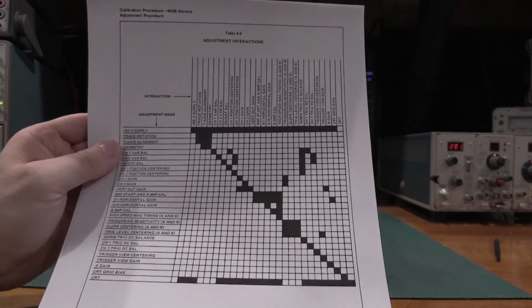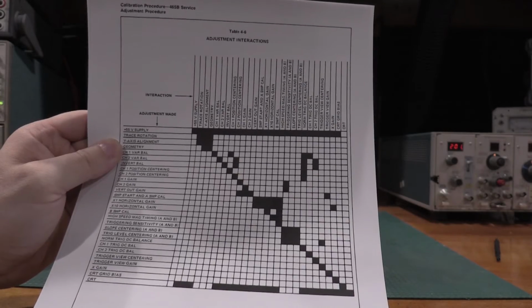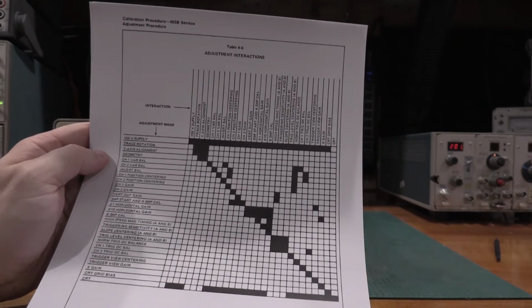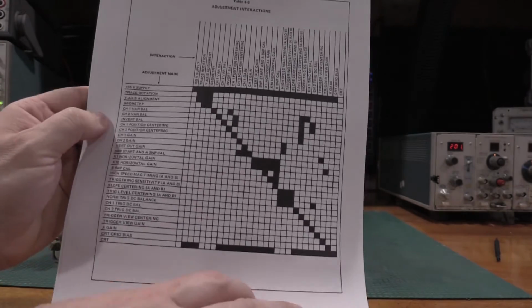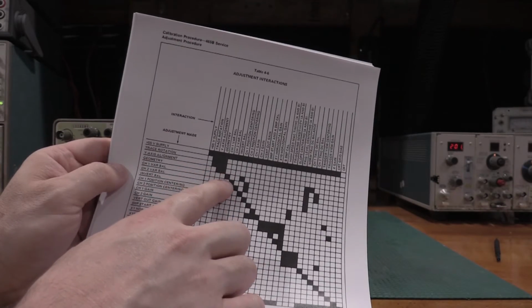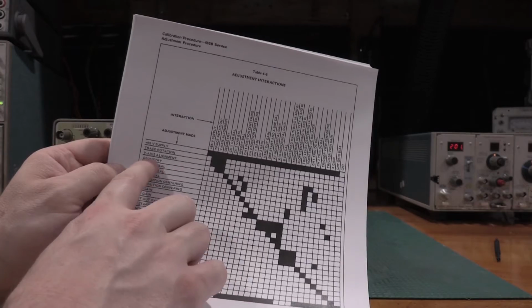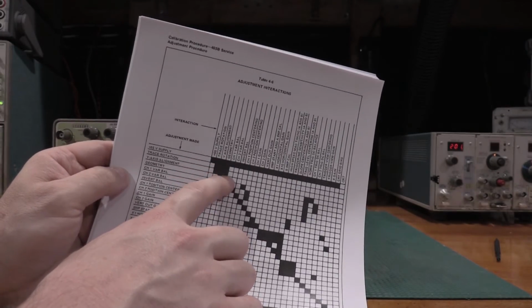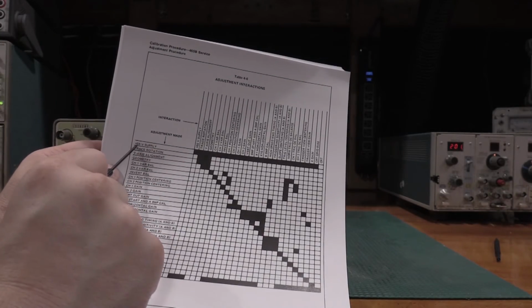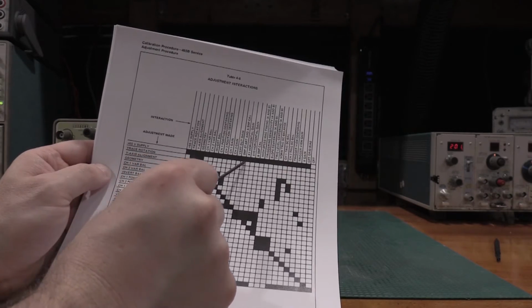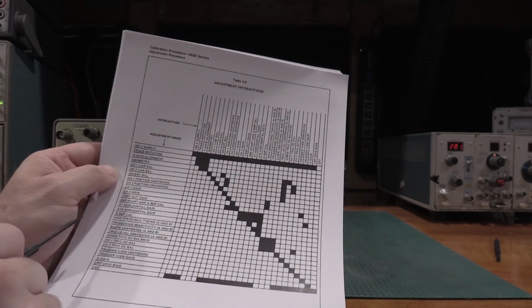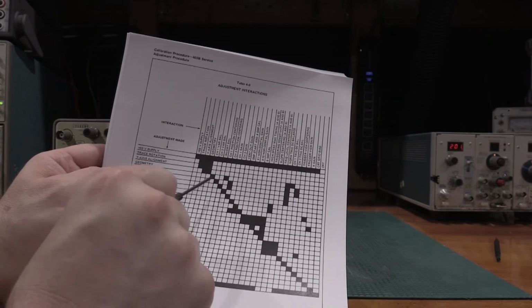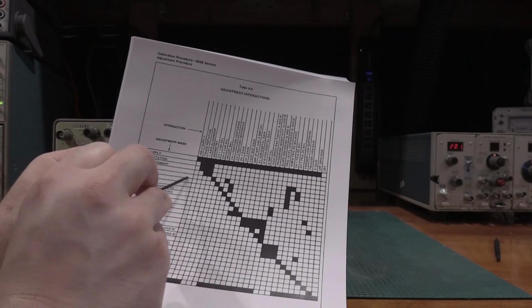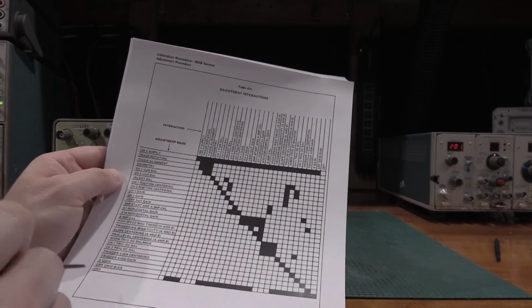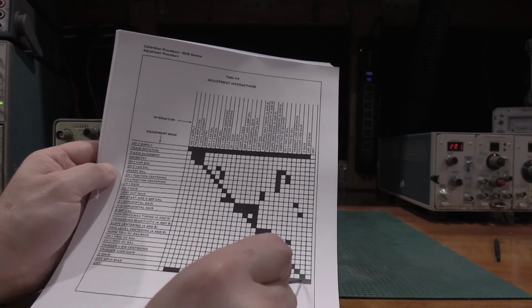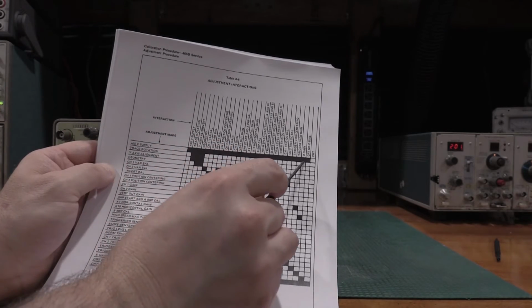Okay, while we wait for the scope to warm up, I figured I'd show you guys the adjustment interactions matrix. This is a cool one that I haven't seen in a lot of service manuals yet. Basically, what it says is if you adjust the geometry, anywhere there's a black box, that will also have an effect. So if you adjust the geometry, it affects the y-axis alignment in the geometry. But if you adjust the 55 volt supply, it affects everything in the instrument except for the CRT. A lot of the adjustments only affect themselves, like the channel 1 variable balance only affects the channel 1 variable balance, doesn't affect anything else in the instrument. Change the CRT, it affects a bunch. Change the 55 volt supply, it affects everything.